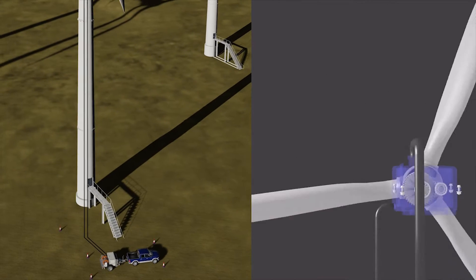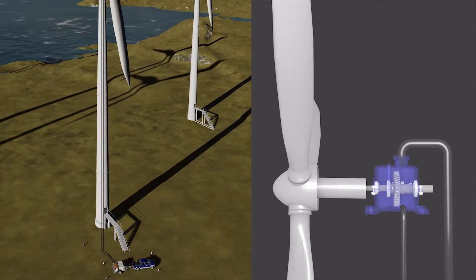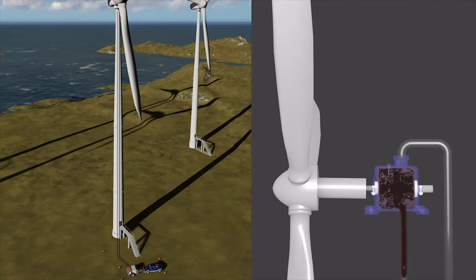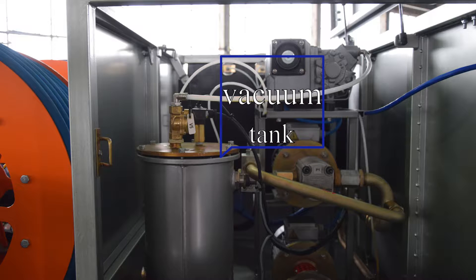The mode of draining used oil: In this mode, the vacuum pump drains the oil from the wind turbine gearbox into a vacuum tank until it's filled, after which the gear pump turns on for further pumping of oil to the prepared container.